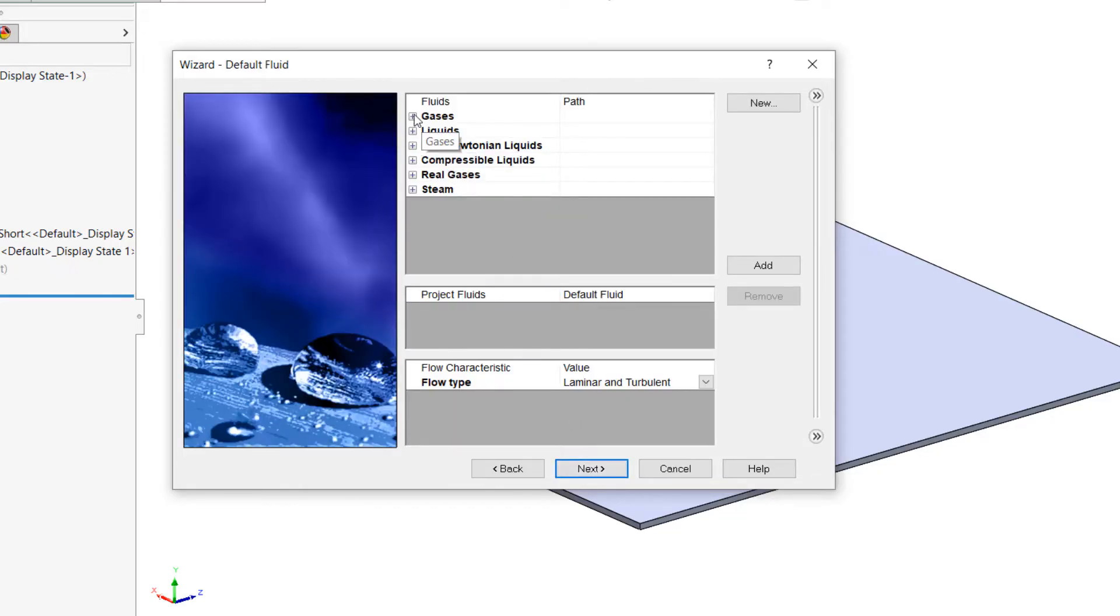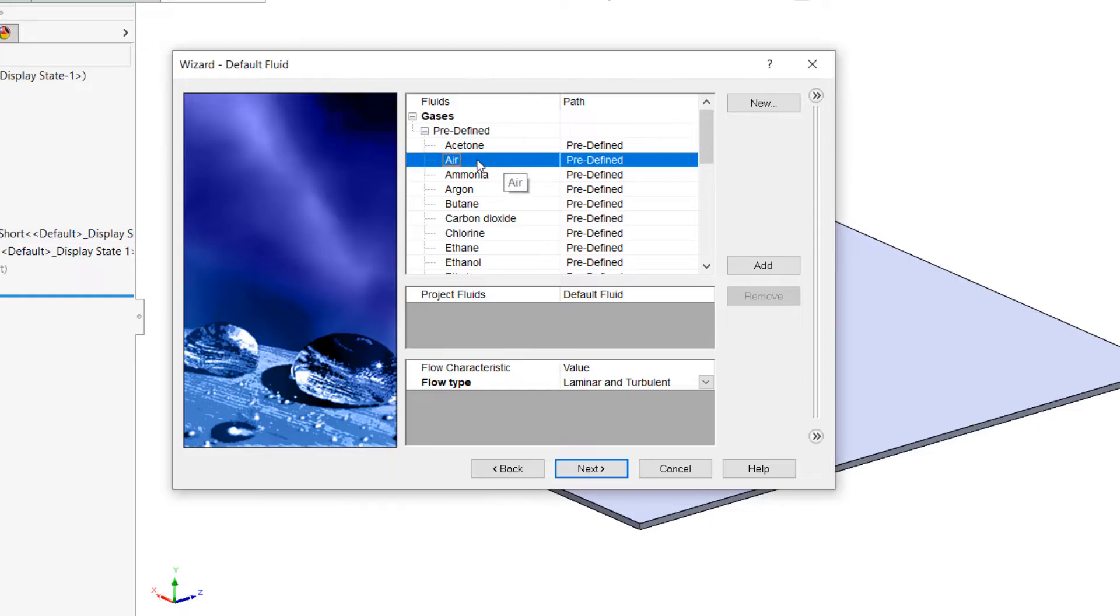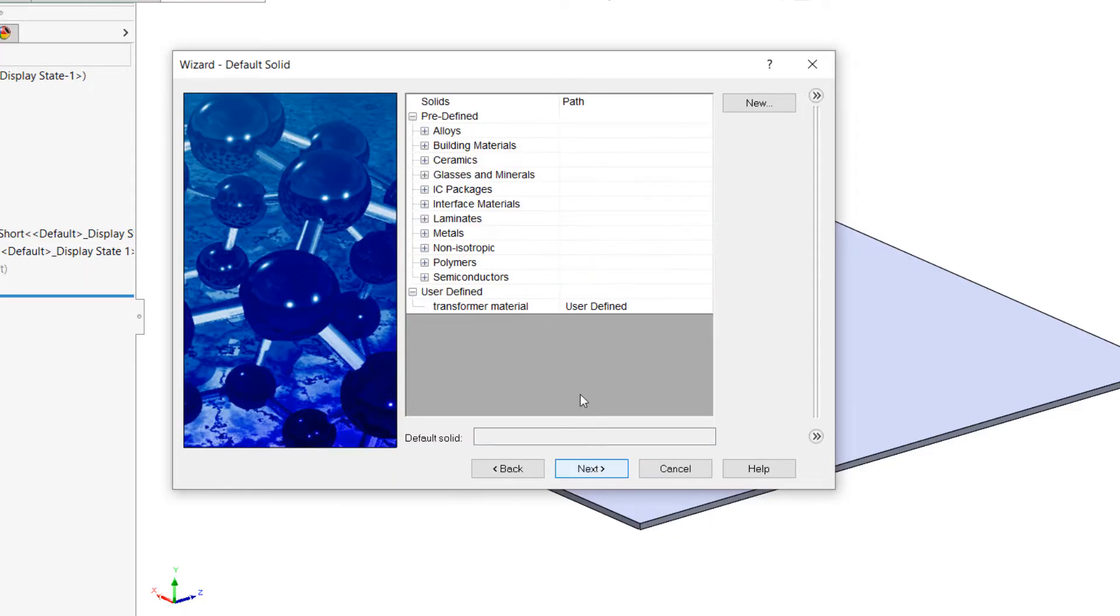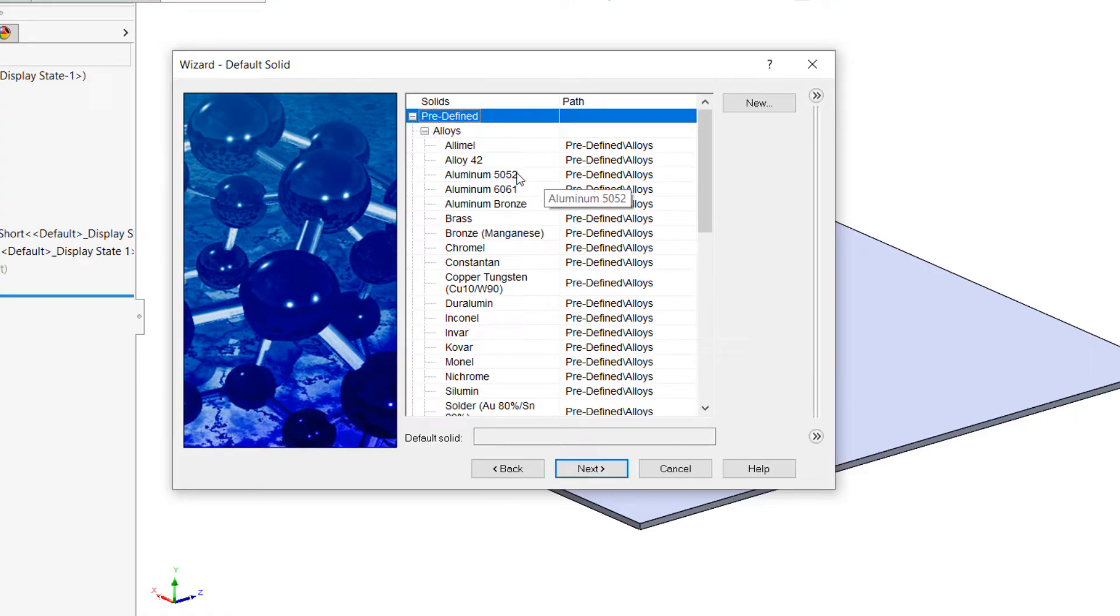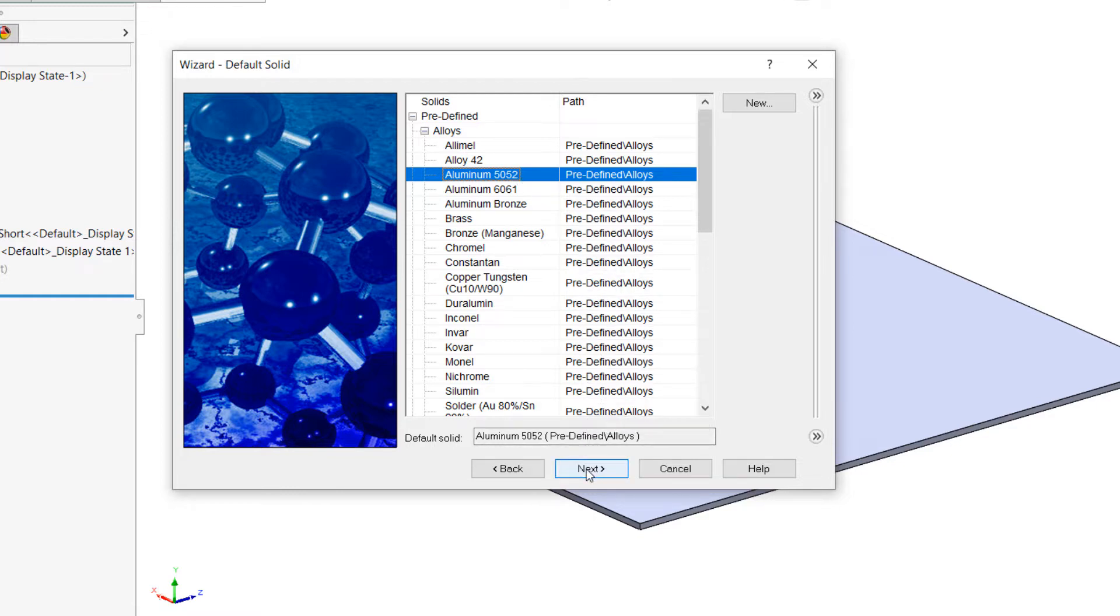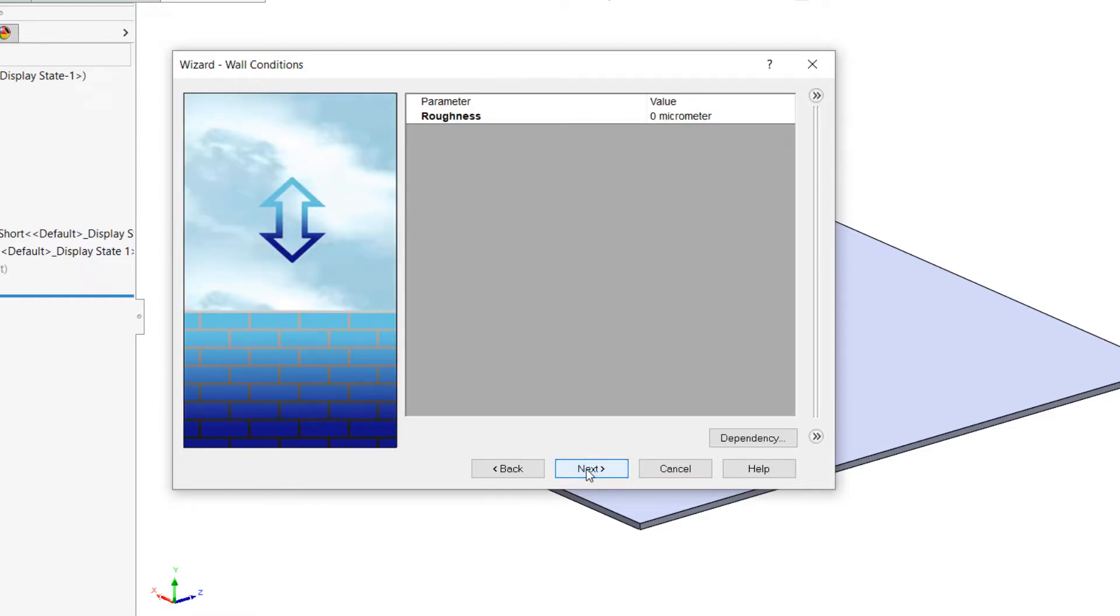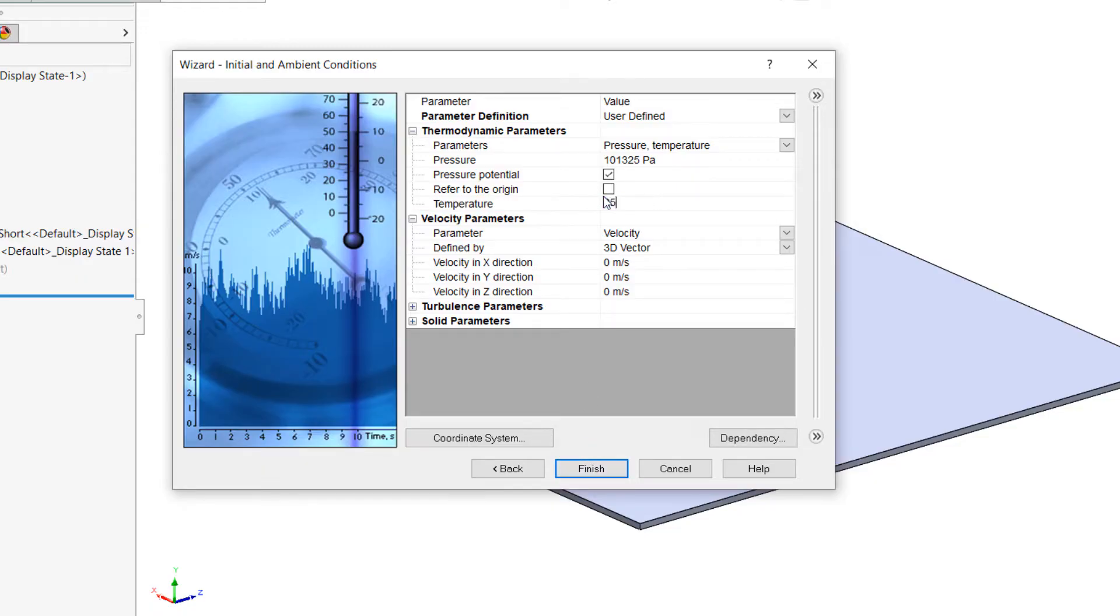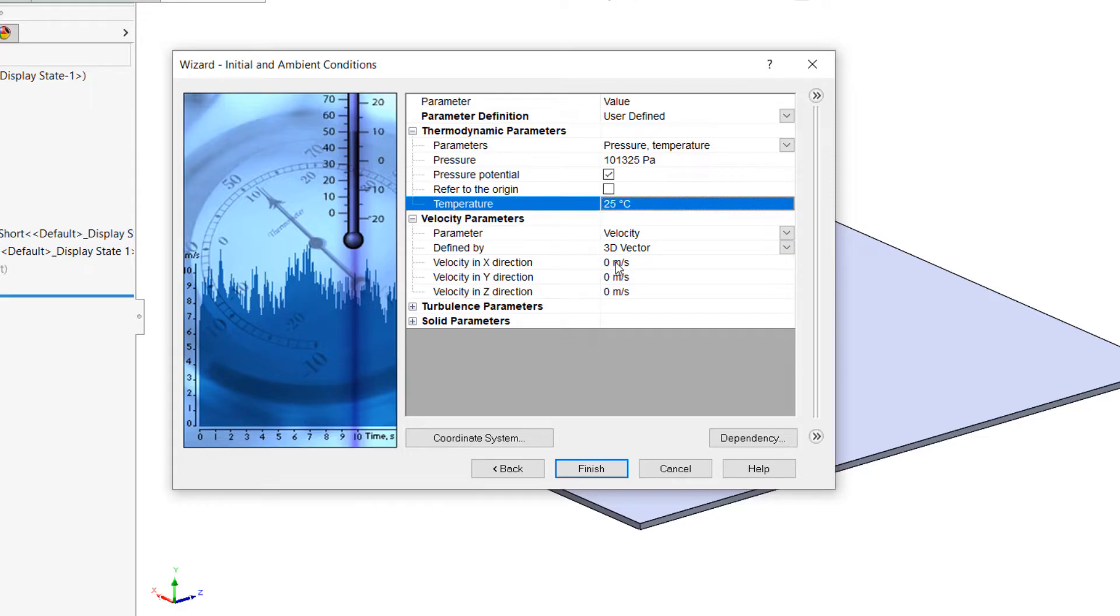For my default fluid, I'm going to choose air. And now we have a default solid screen, and I'm going to choose aluminum 5052. This will be applied to all components that don't have a specific material applied to them. On the final screen, I'll input my ambient temperature, which is going to be 25 degrees C, but this could be raised for elevated temperature testing. We could also input velocity for the flow in any given direction, but for a natural convection problem, I want to leave all of these at zero.